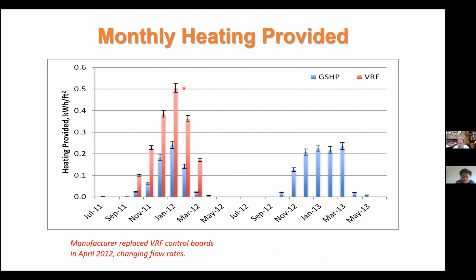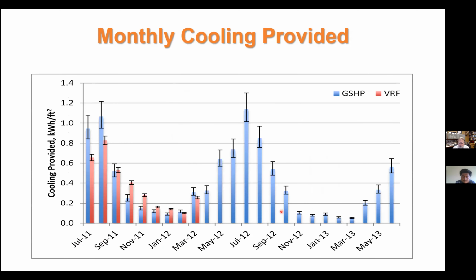So I show some error bars here for our results, but this is the monthly heating provided. You can see in this first winter, the VRF system is providing more heating than the ground source heat pump system. And you can see here we've got the ground source heat pump system for the second year. Then the monthly cooling for the ground source heat pump system is generally higher. And if you compare the scales on the two slides, you see the ground source heat pump system at peak is providing much more cooling than the difference in heating on the previous slide.